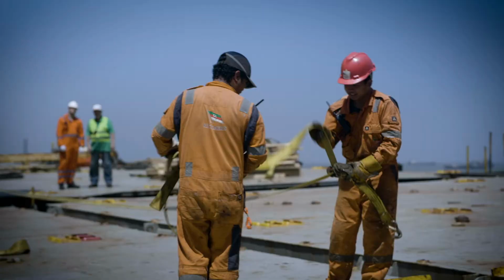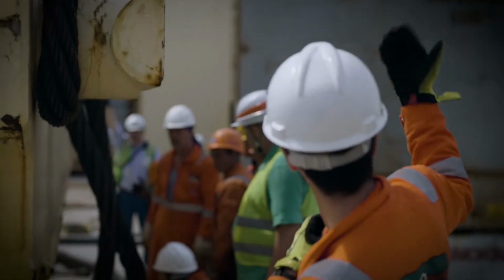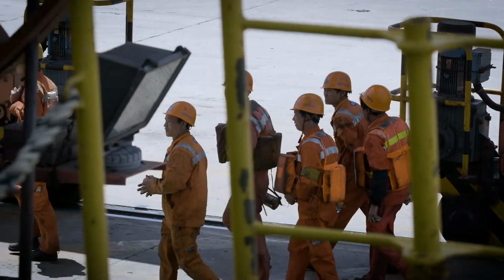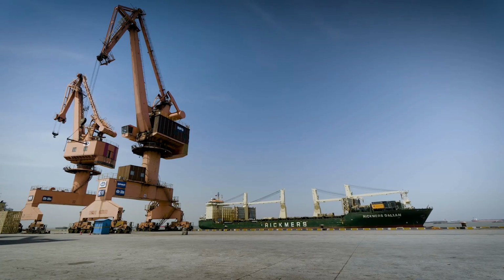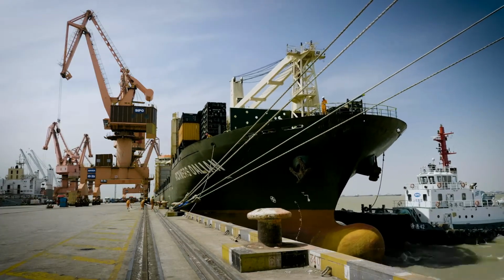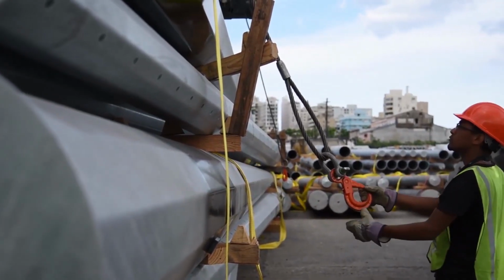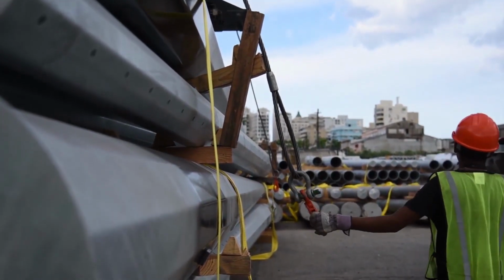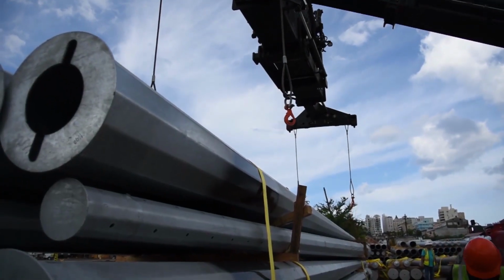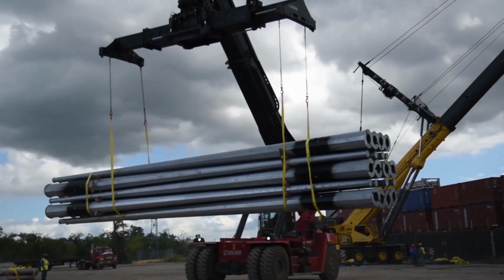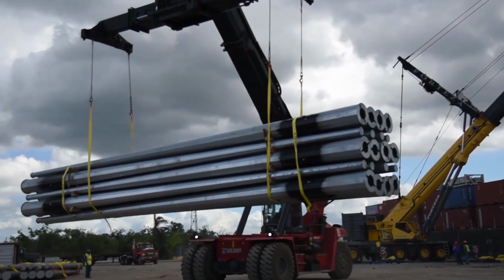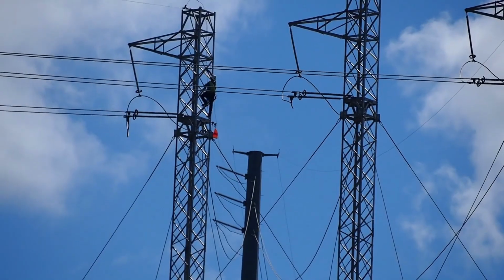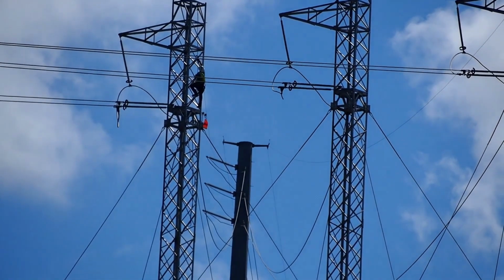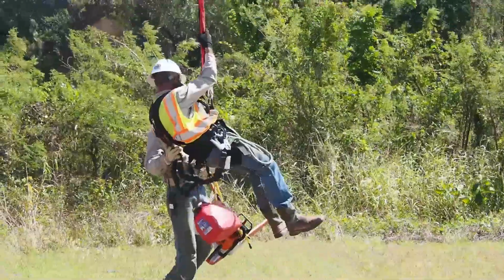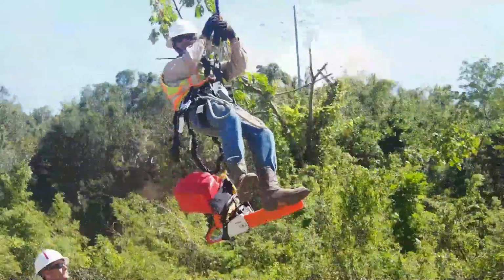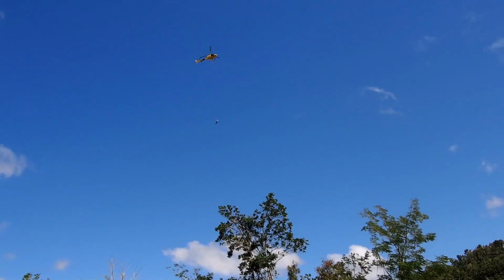General restoration footage can make this process look fast because emergency crews move with urgency. Lines can be restrung, poles can be replaced, roads can be cleared. But those visible operations are not proof that a large power transformer can be replaced on the same schedule. The distinction matters. Grid restoration is a coordinated response across many kinds of equipment. The largest transformer may be only one element, but it can carry a manufacturing and logistics schedule that is much harder to compress. That leads to the obvious resilience question.